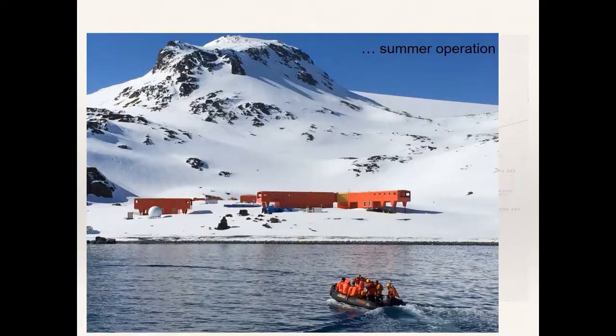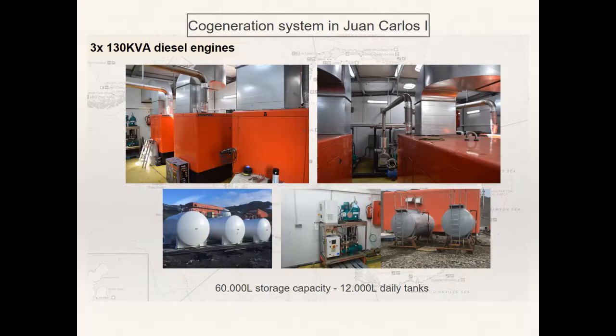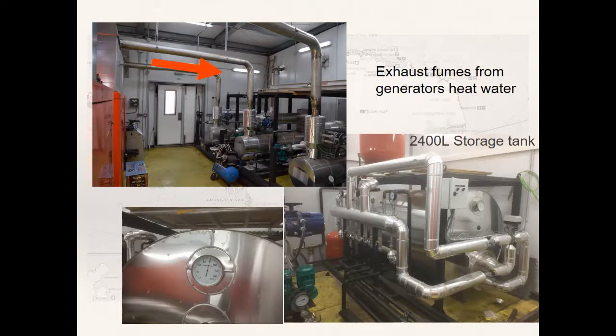During the summer, at Juan Carlos I station and after its renovation, the power supply is based on the use of 3 diesel generators of 130 kVA each, compared to the 2 40 kVA generators that the old station had, and also a storage of 72,000 liters of diesel is available. In addition, to take advantage of the energy produced, a cogeneration system was installed during the rebuild to use the smoke from the generators in the production of heat.